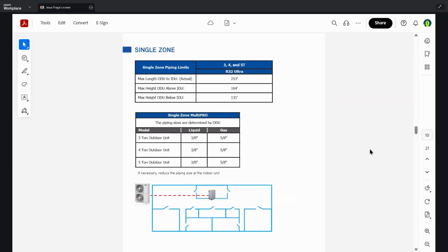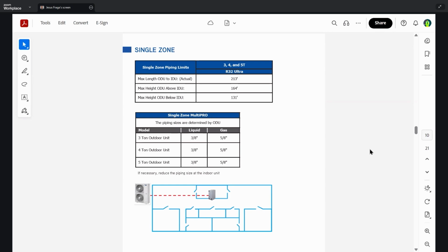Moving on here. This is our single zone piping limitations. So this chart pretty much gives us the max length ODU to IDU, the max height ODU above IDU, max height ODU below IDU, and we know those values are 213, 164, and 131 feet.